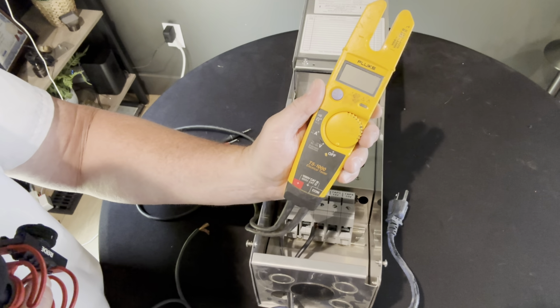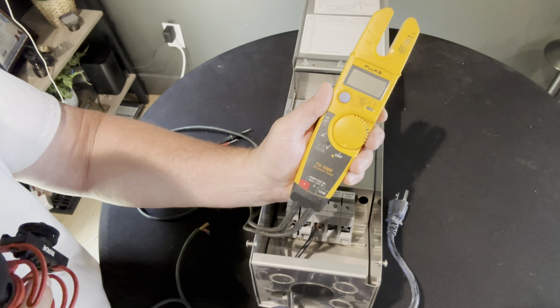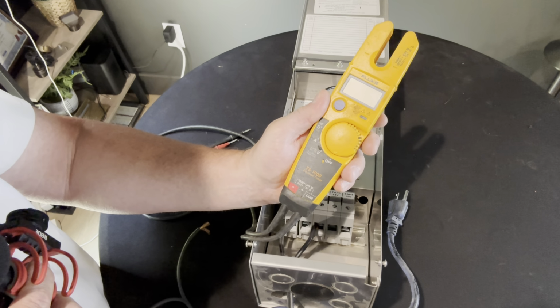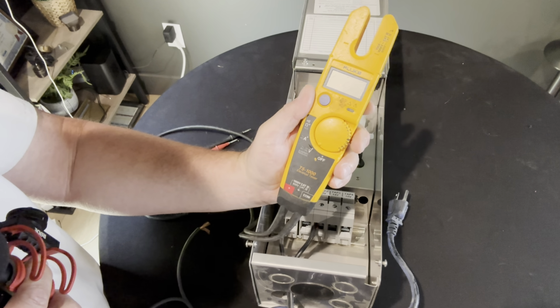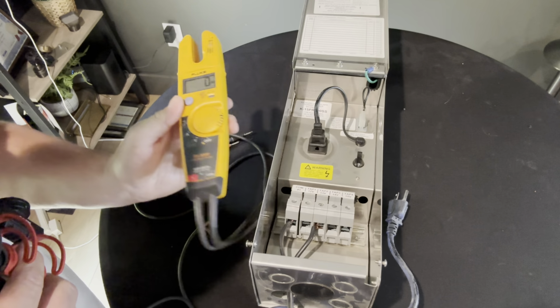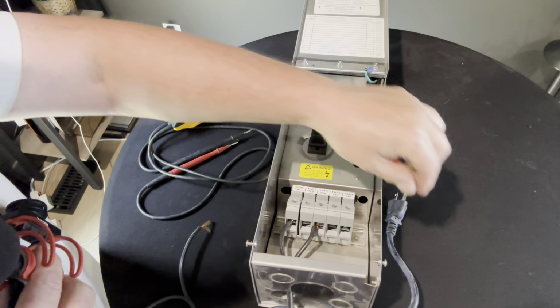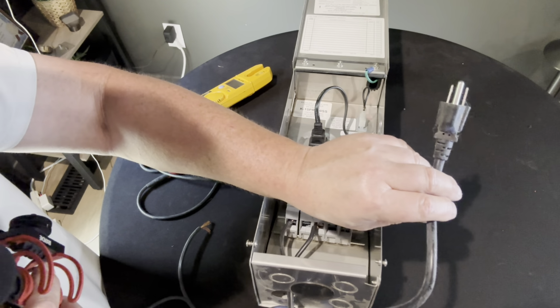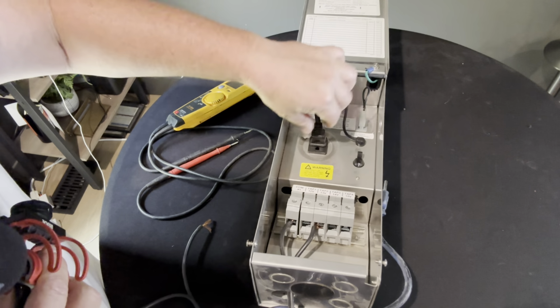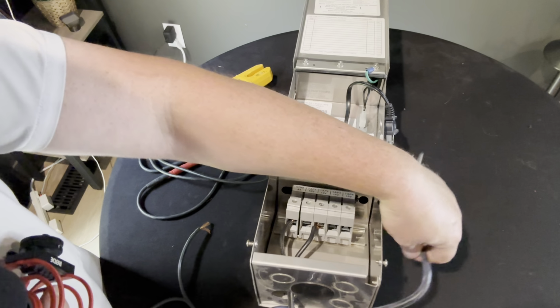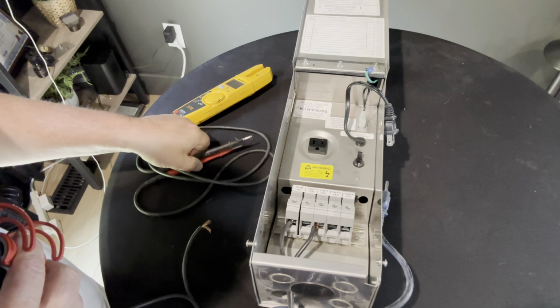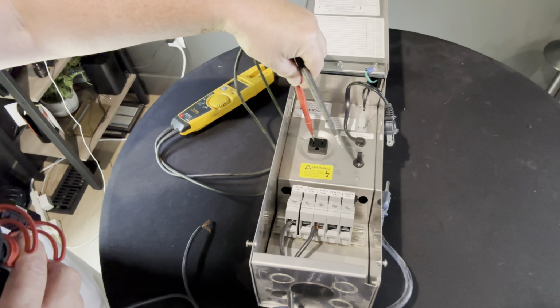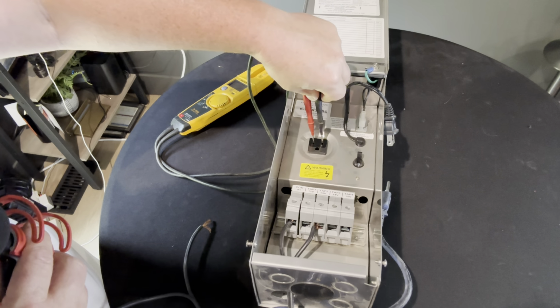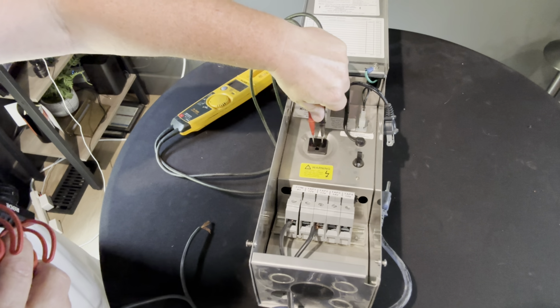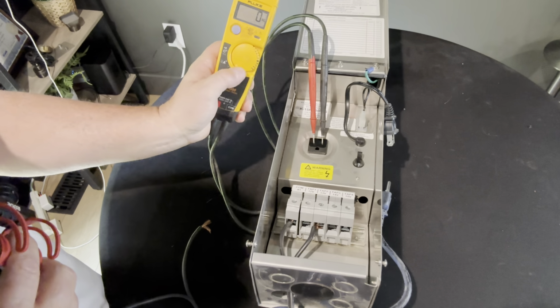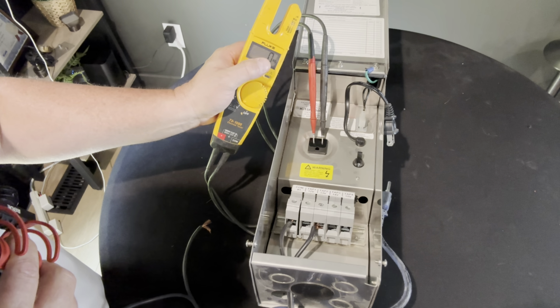The first thing that we talk about doing is testing the primary voltage at the transformer. So what we would do is to move our meter onto the V for the voltage. Then if our transformer is already plugged into an outlet, you could test the outlet, or you can come over to your transformer, assuming that your main pigtail is plugged in. And then you can come in here, and it doesn't matter which one you do. You could put in your probes and put them into here.